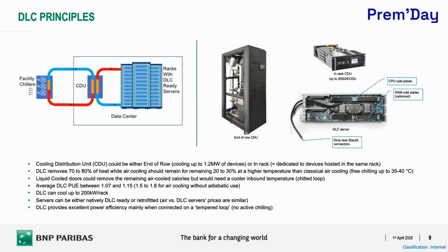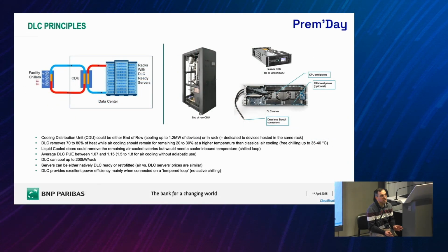A CDU is basically pipes and pumps, so it's quite cheap. When you compare the cost of the CDU and the cost of the impact, you may choose to put 2 of them. That's what we did. The liquid system is removing 70 to 80% of the heat from the servers, which means that you need a residual system to cool with air the RAM and the different devices on the motherboard of the servers. And there are also ways to do that with a liquid cooled door. That's what we did actually in Norway.